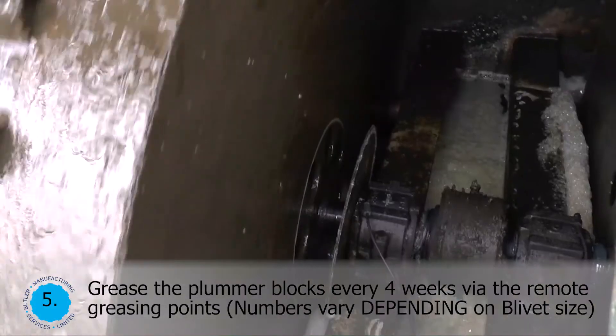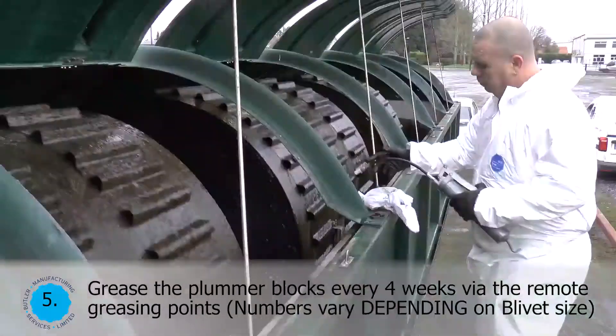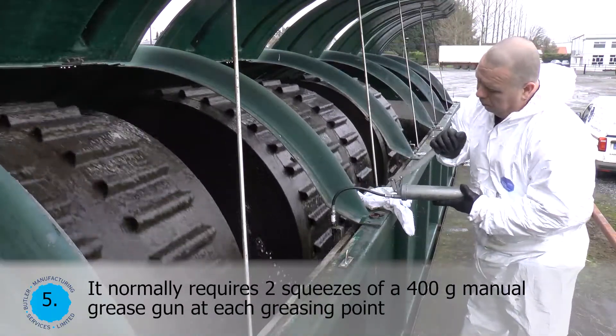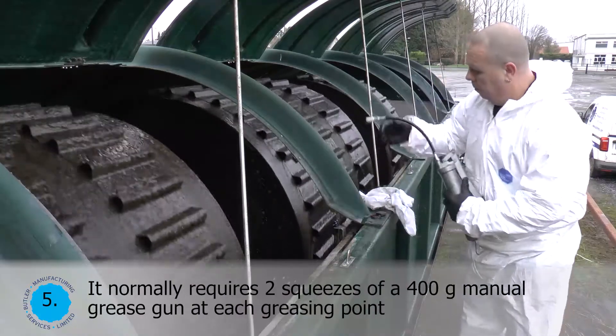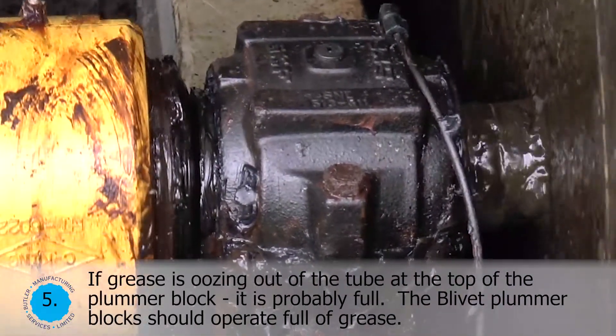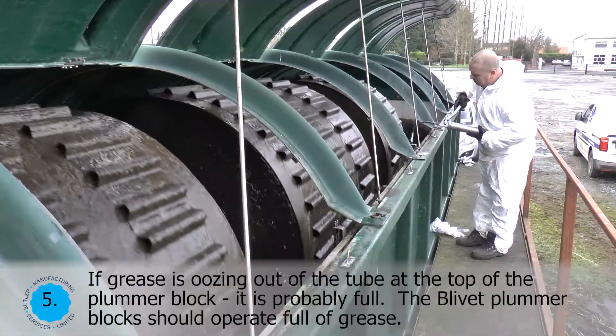Grease the plummer blocks every 4 weeks via the remote greasing points. Numbers vary depending on blivet size. It normally requires two squeezes of a 400 gram manual grease gun at each greasing point. If grease is oozing out of the tube at the top of the plummer block, it is probably full. The blivet plummer block should operate full of grease.